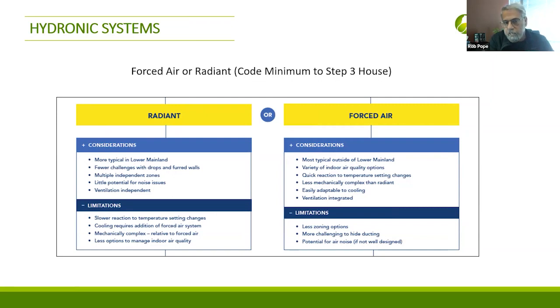So it has a slow reaction time. If you need cooling in the house, and as houses get more energy efficient, cooling starts to become the dominant load, this is one of the limitations. Radiant can do a partial amount of cooling, but it's complex. It can never do all the cooling. So if you need cooling, you need a forced air system to do that properly.